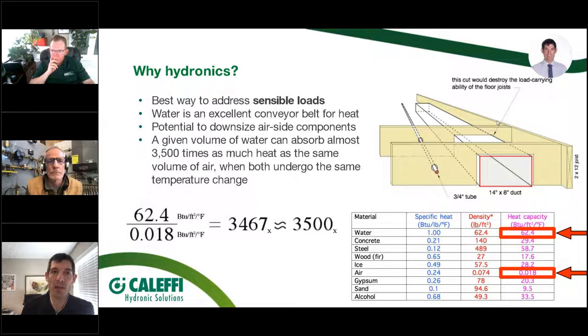And that's important for a few different reasons. If you're an architect looking at this slide, and we're going to move the same amount of sensible heat with a 3/4 inch piece of PEX versus a 14 by 8 inch duct, that's a big upgrade. That's aesthetically going to be nicer. We can squeeze that into a few more places. It's going to be easier to do all that. And it's just the best way to move that sensible energy around.